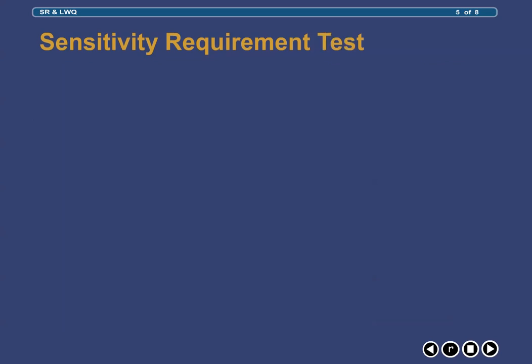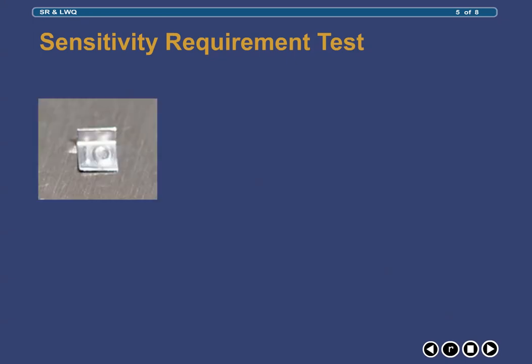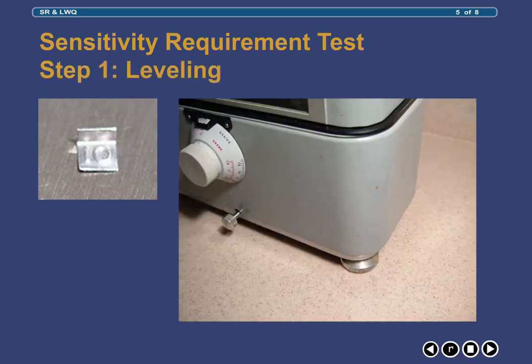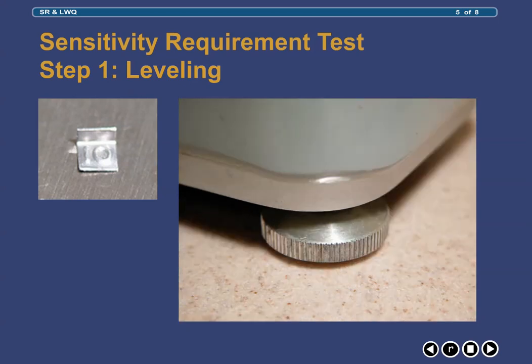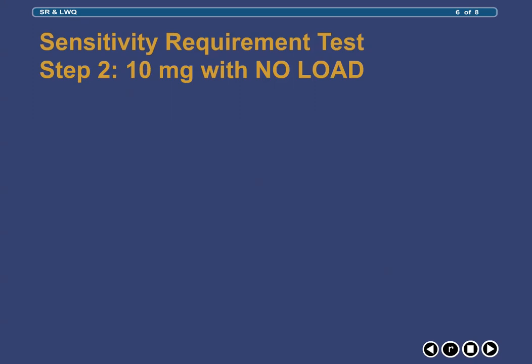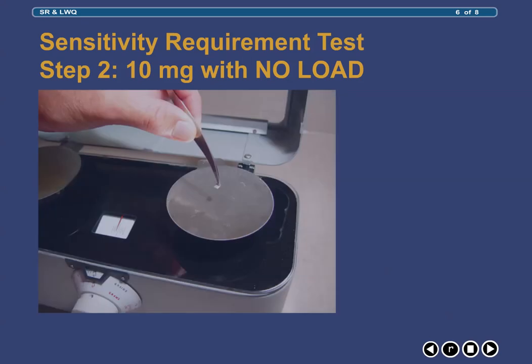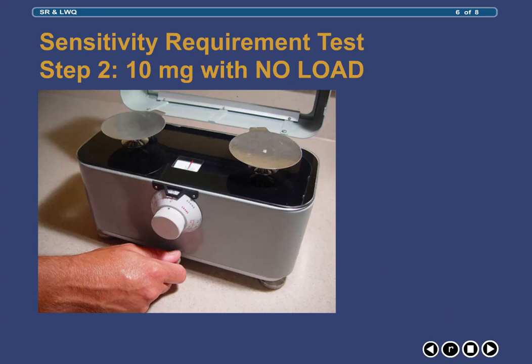In order to ensure that your balance conforms to the accepted sensitivity guidelines, you can easily perform a simple sensitivity requirement test utilizing a 10 mg weight. The first step in this test is ensuring that your balance is level by rotating the leveling screws at the base of the balance until the long center mark on the scale is in alignment with the pointer. Once you have ensured that your balance is level, you should then place a 10 mg weight on one of the empty pans, then release the locking arm so the pans move freely.